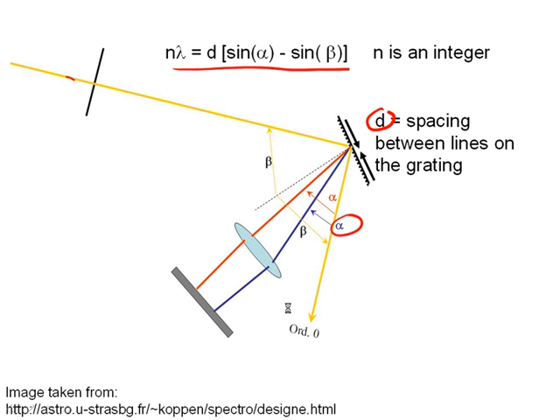And of course, the way this device works is the light comes in and hits the grating. Most of the light reflects, but some of the light is diffracted as a function of color. And we can collect that light and look at it on some kind of detector or a screen with a hole in it. And this is the site that I got this image from.